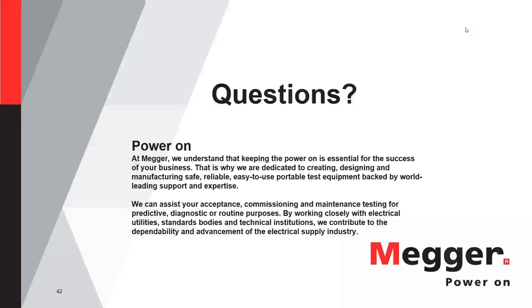This comes from Ryan. He asks, since EPR materials can vary much more than XLPE, does the breakdown voltage of oil vary as much? Or is the oil breakdown voltage fairly constant? Okay, first of all, the first part of the question is not related to the second part. These variations that I described are mainly important for the TDR, that the velocities on EPR vary more than on XLPE because the base material is just supplied to all the cable manufacturers from one company. So the EPR is not, there's one main manufacturer, but the other manufacturers are also making EPR and everybody makes their own compound. So that has to do with the TDR, not the breakdown strength.